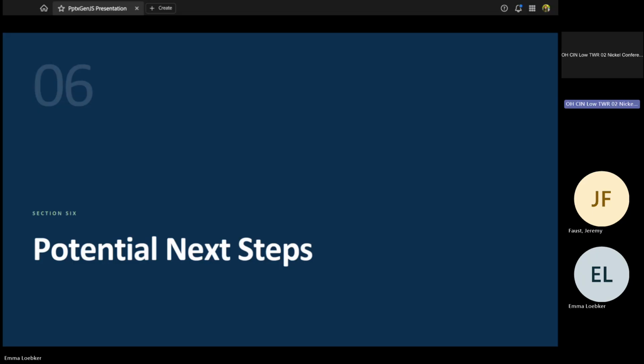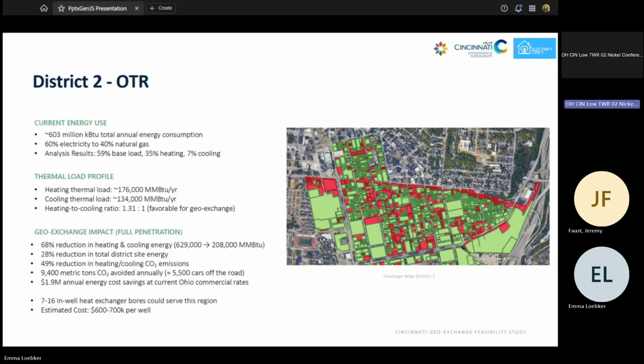Just one point I wanted to mention - in both of those districts, one of the key findings was a 1.31 to 1 ratio in heating demand to cooling demand. The reason that's important is it tells us the heating and cooling loads are very balanced, which is really what you'd expect for our region - we have a mixed, fairly balanced climate. What that means is if all of these buildings were interconnected, you would see those highly balanced loads that are extremely beneficial to district systems, because it allows you to drastically reduce the total capacity you need to install, making the first cost more favorable.